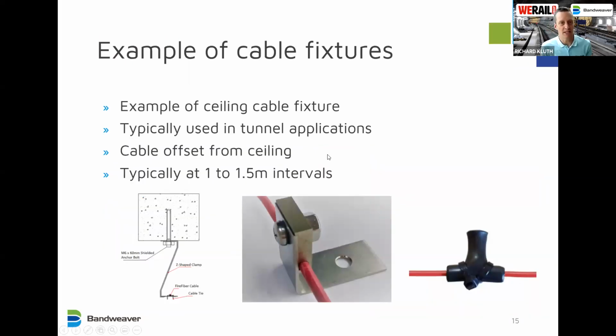The cable needs to be attached somehow. Here's an example of some cable fixtures typically used in tunnel applications. These are usually attached to the ceiling and the wall. And depending on the tunnel, the different partners, the different customers, different styles of fixtures are used, but they have a commonality in which the cable is usually attached to the fixture at an offset from the wall or ceiling to maximize the sensitivity, and typically they're installed at intervals of 1 to 1.5 meters.